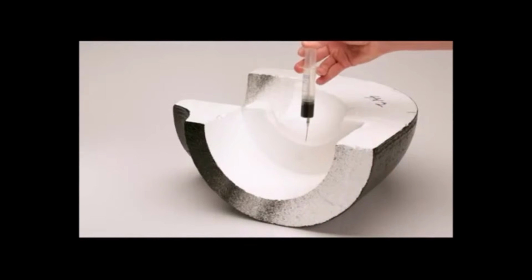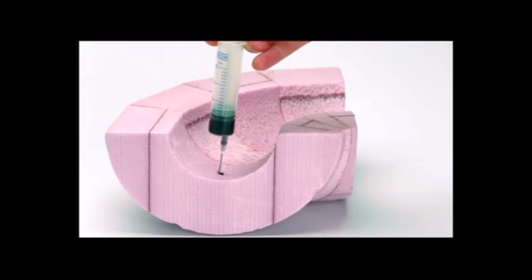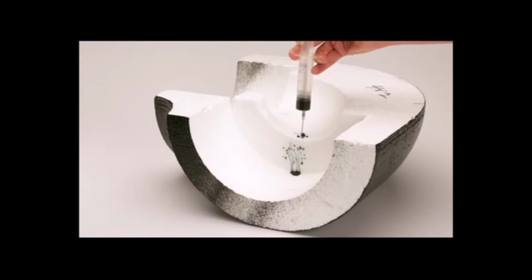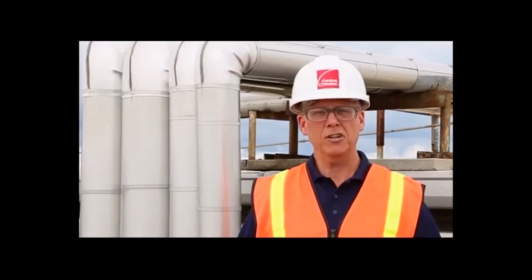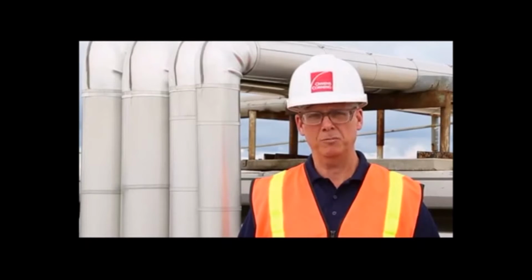In higher density EPS products, the fusion of the individual beads is better than lower density EPS products, but the problem still exists, as shown with this visual demonstration utilizing pipe insulation made from a FOAMULAR XPS fabrication billet versus 2-pound EPS pipe insulation. In an installation like this, it's critical to have moisture-resistant materials.